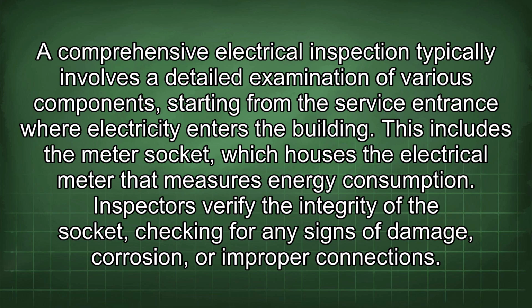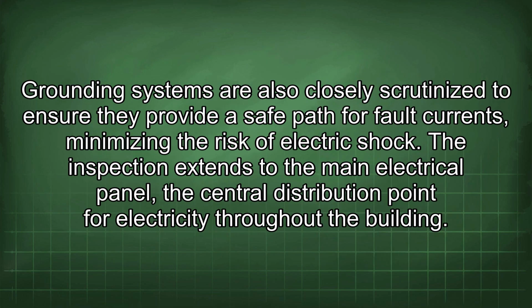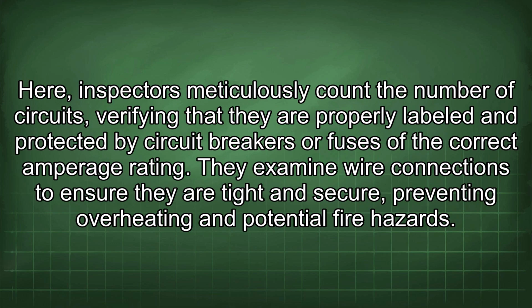the building. This includes the meter socket, which houses the electrical meter that measures energy consumption. Inspectors verify the integrity of the socket, checking for any signs of damage, corrosion, or improper connections. Grounding systems are also closely scrutinized to ensure they provide a safe path for fault currents, minimizing the risk of electric shock. The inspection extends to the main electrical panel, the central distribution point for electricity throughout the building. Here, inspectors meticulously count the number of circuits, verifying that they are properly labeled and protected by circuit breakers or fuses of the correct amperage rating.